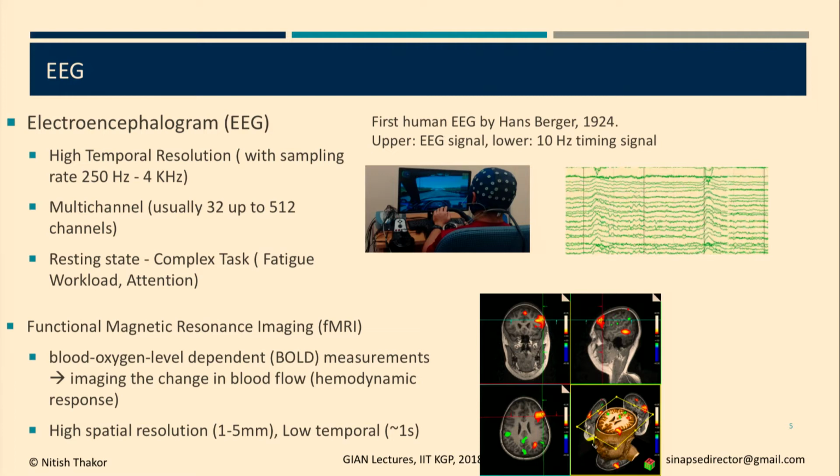So, how do you get a lot out of EEG? Well, you can do high resolution EEG. I mean, most of the time in the lab you are doing 0.5 to 100 hertz, but there are higher frequency bands like gamma and high gamma. I think if you go beyond high gamma, 150 hertz or so, there isn't much information. The signal power is too low, and I had shown you a spectrum for that. So, the gamma band power is very low, and so you can sample at 250 hertz to few kilohertz.